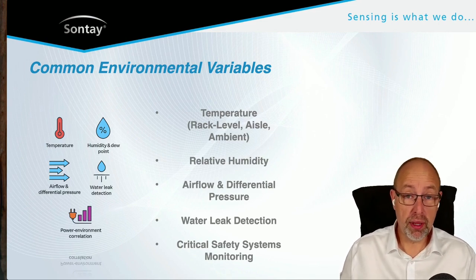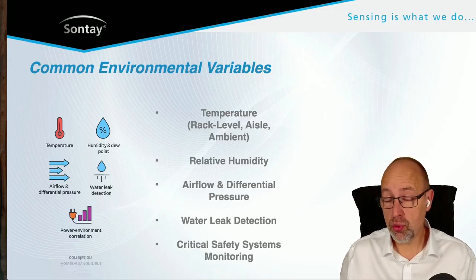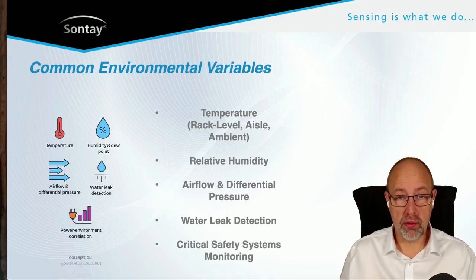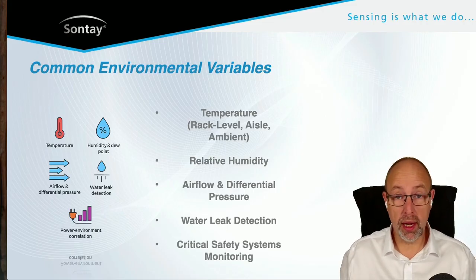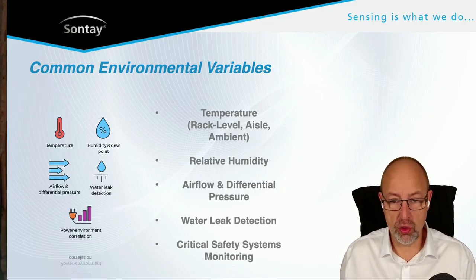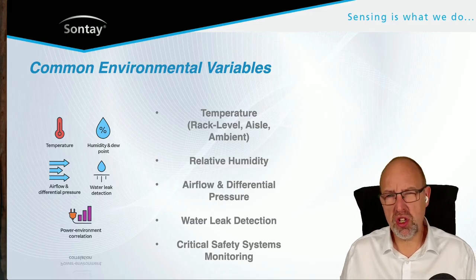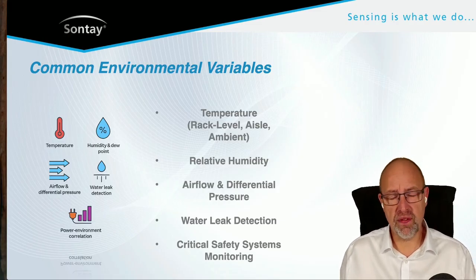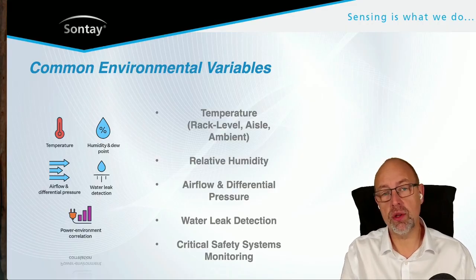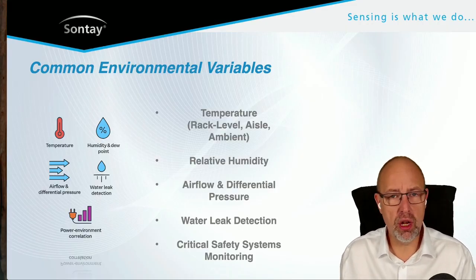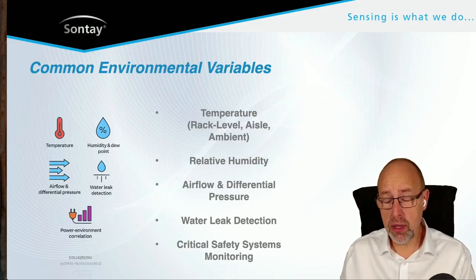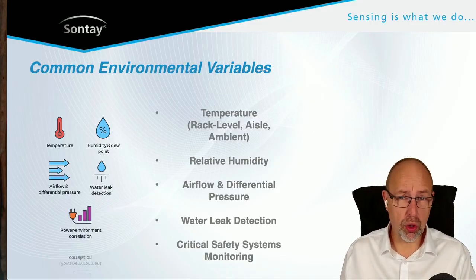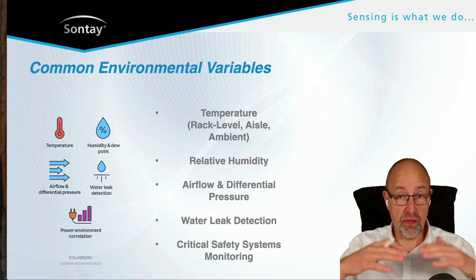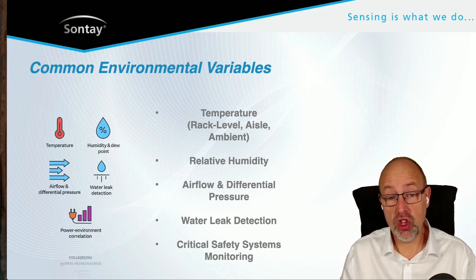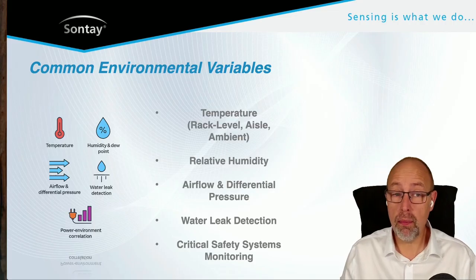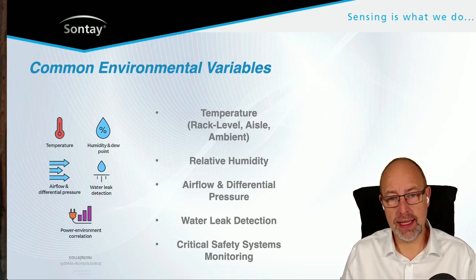If water builds up under the floor, that's where all your cables are running, so it could cause huge problems before you'd even notice. That's why leak detection is often built into the air handling units themselves, giving an early warning. Even tiny leaks, like minuscule leaks on chilled water coils, or condensate overflowing a drip tray, can be hugely detrimental. Leak detection is a really important factor in data centers.